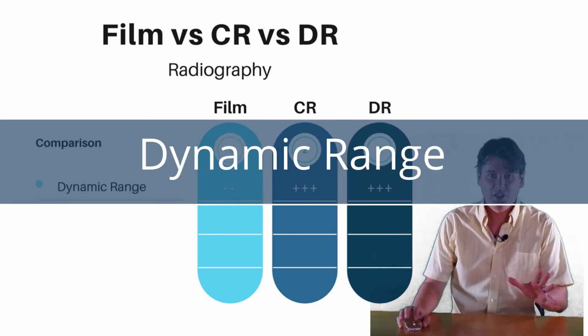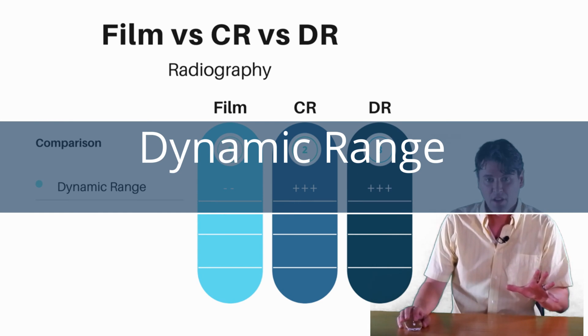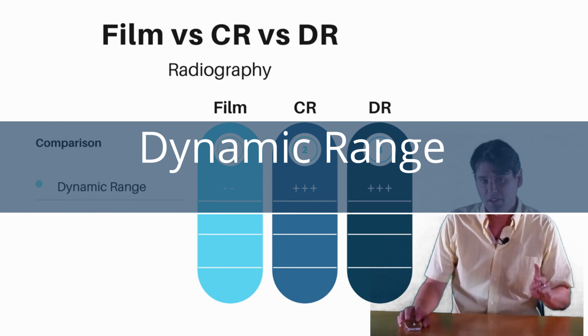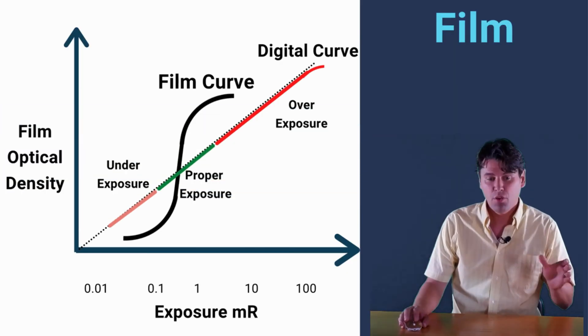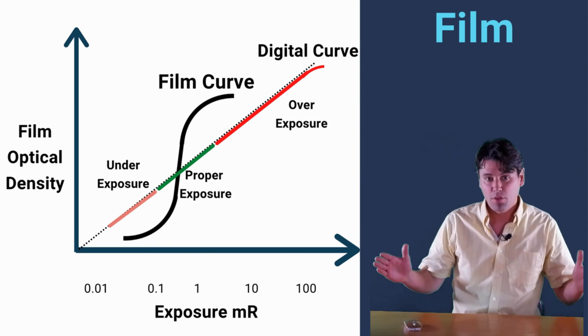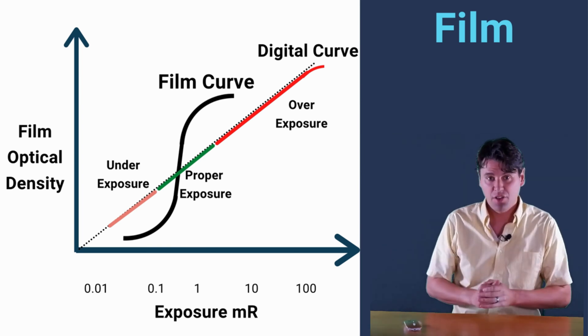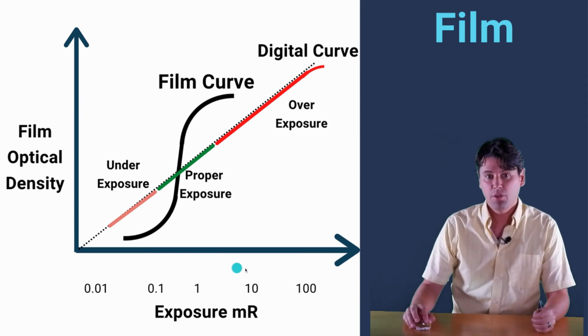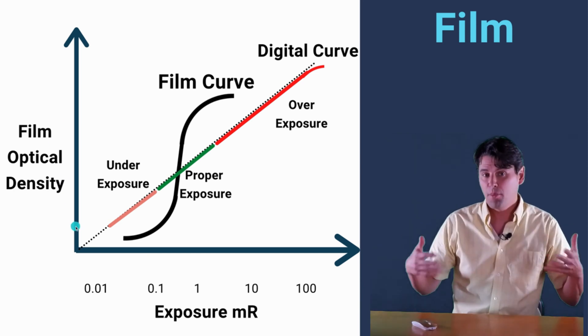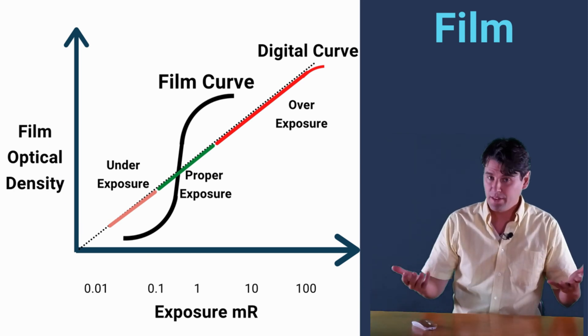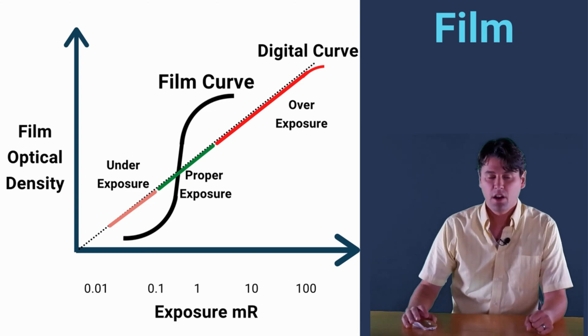One of the big advantages is dynamic range. We have a video where we described dynamic range before, but it's basically the ability to make a good image even over a wide range of radiation dose exposures. On this axis we're plotting the radiation dose that the image receptor sees, and on this axis we're plotting the film optical density or the digital number in the CR/DR system.